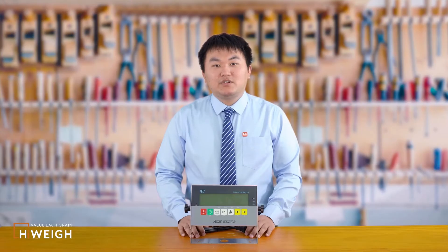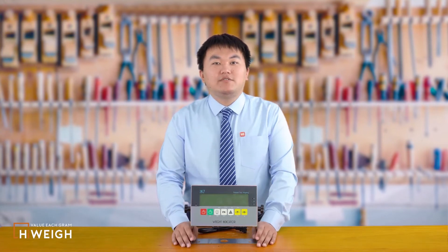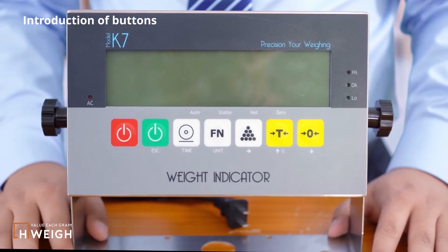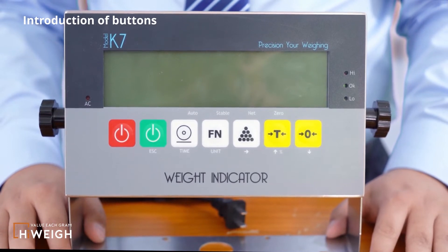I will demonstrate how to enter and modify the configurations of the K7S, including parameters such as division and capacity. Let me introduce the functions of the seven buttons first. In the normal weighing state, from left to right are: the shutdown button, the power on button, the print button, the function button, the accumulation button, the tare button, and the zero button.